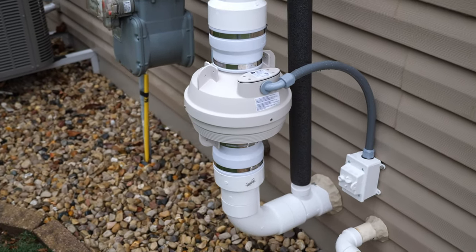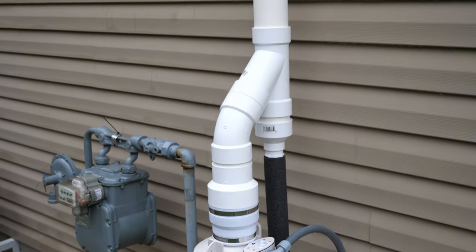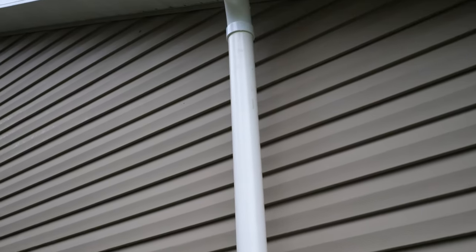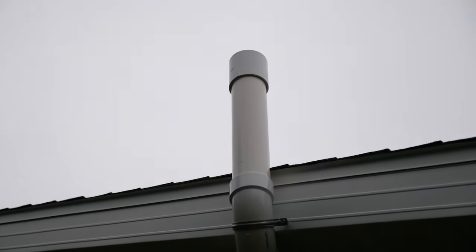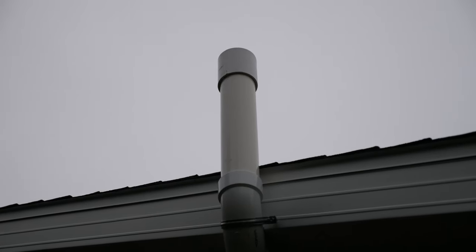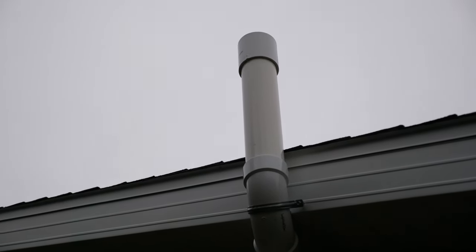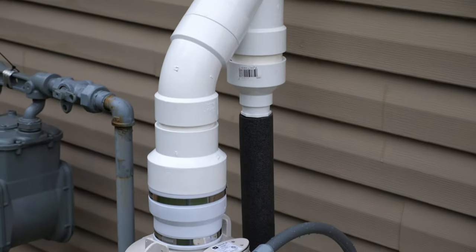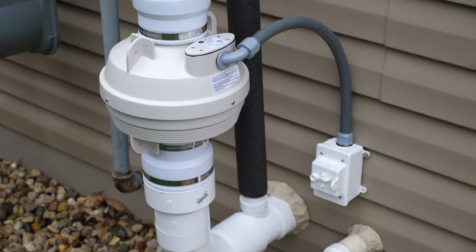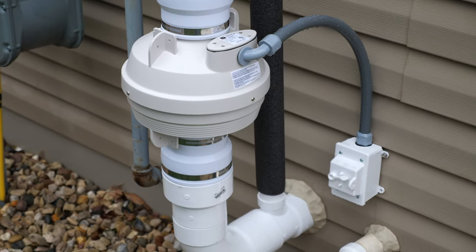I put some insulation around the drain to help keep it from freezing — the manufacturer said that's something you can do. The vent pipe goes right up the side of the house, and at the top I've got a coupler with a quarter-inch screen to keep any animals or debris from getting in. You're not supposed to put any elbows on the top to redirect it sideways; it's supposed to go straight out. The screen is usually acceptable by code in most areas. Power comes out connected to a GFI outlet, so if there's any issue with moisture it will trip and prevent electrical problems.